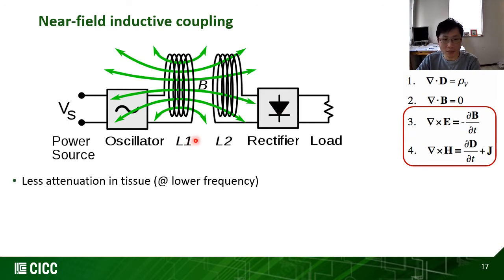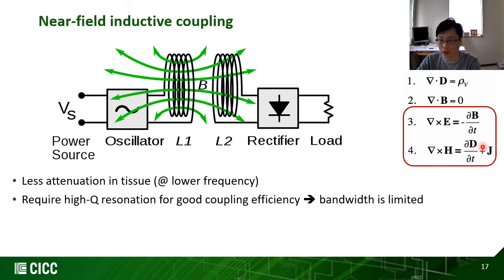They typically operate at lower frequency because that leads to lower attenuation. Since it's mostly magnetic induction, it's also better for tissue heating, which I will discuss later. This type of inductive propagation requires resonation to increase the quality factor so they can get good coupling efficiency. Because of that, such inductive coupling cannot achieve a wide signal bandwidth.